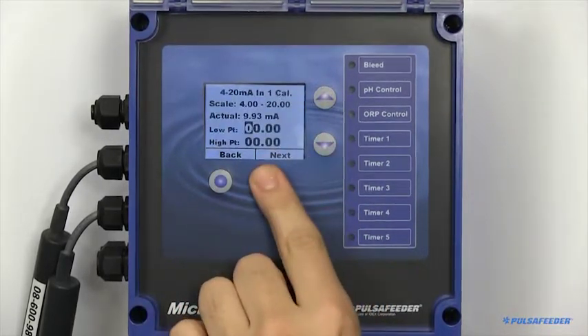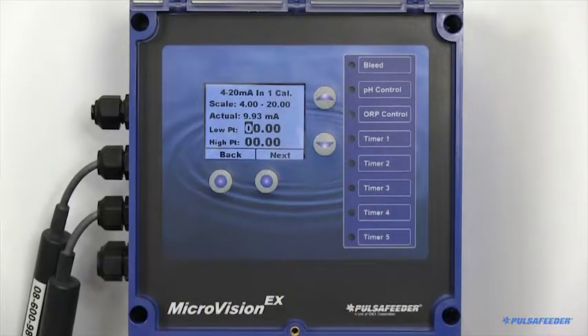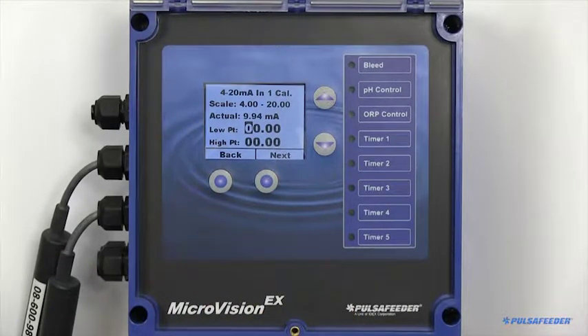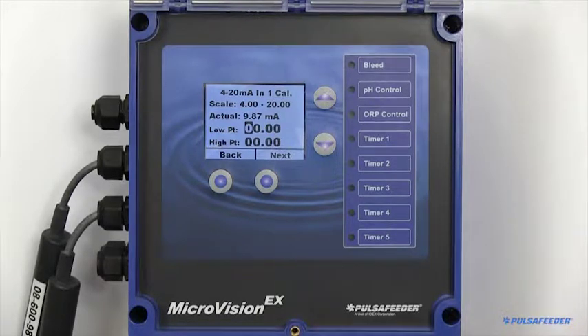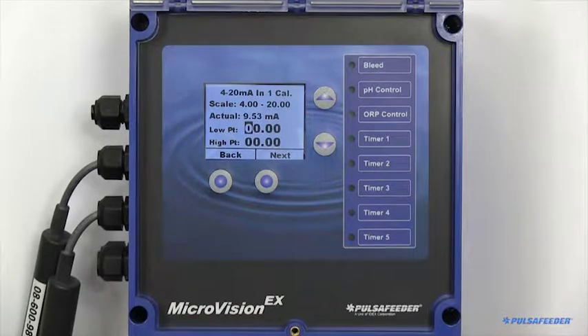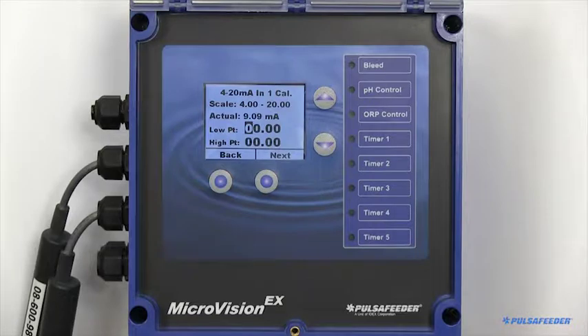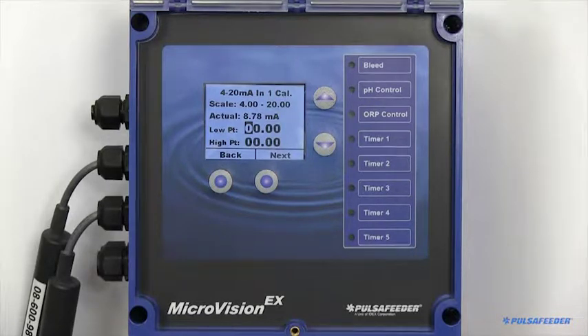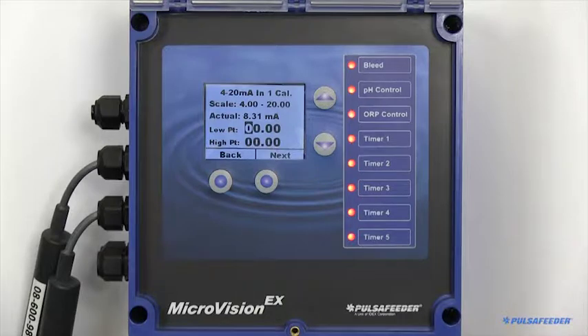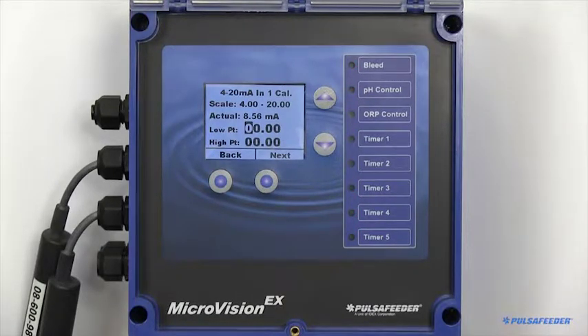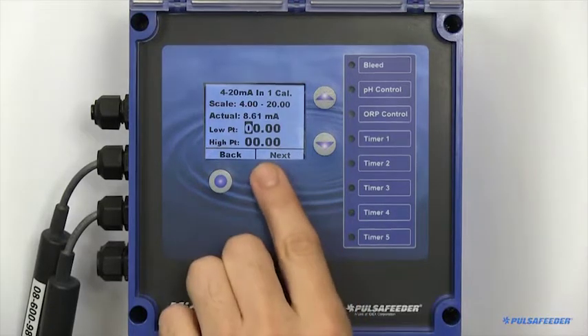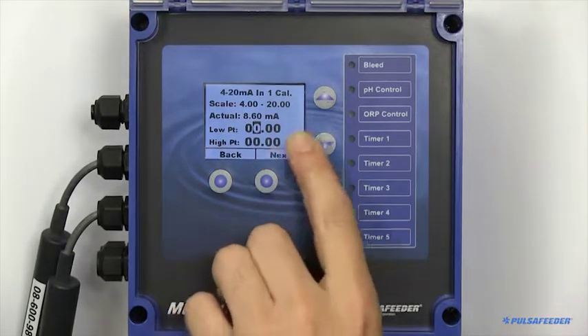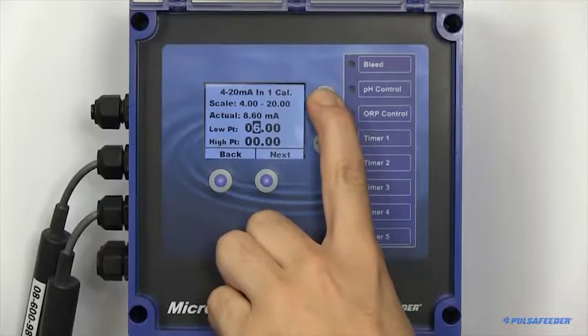You may need buffer solutions to perform this. The top row indicates your low point. The bottom row is the high point. You will need two buffer solutions. Place your probe in its low buffer solution. Wait for the unit to adjust. Enter the correlating value into the controller, and enter through just the top row.